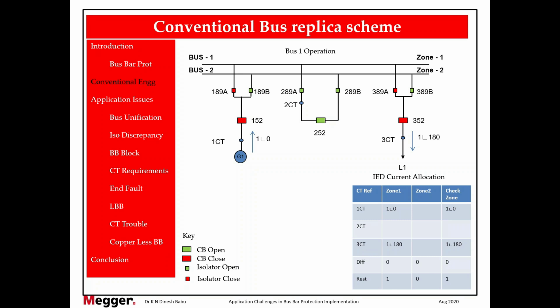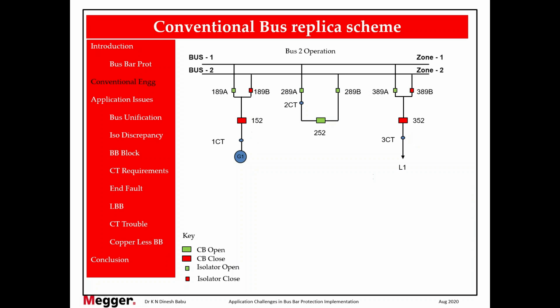Second question, earthed towards which bus? That actually depends on the isolator status. So whether it is bus 1 or bus 2 makes no difference. It is earthed towards the bus. If you close 89A, it is earthed towards bus 1. If you open this and close 89B, it is earthed towards bus 2. That's the concept. Moving on, second example.